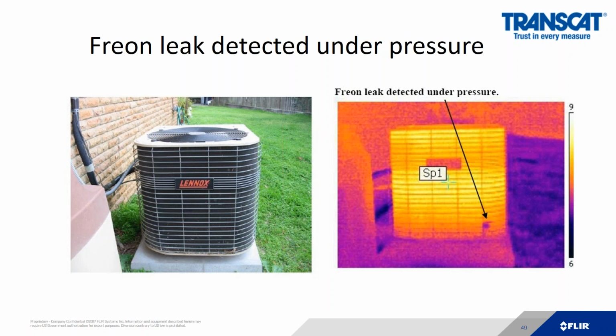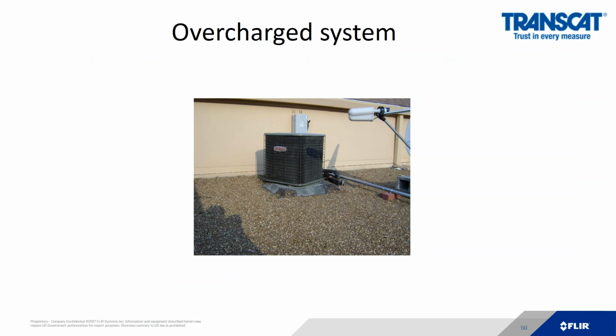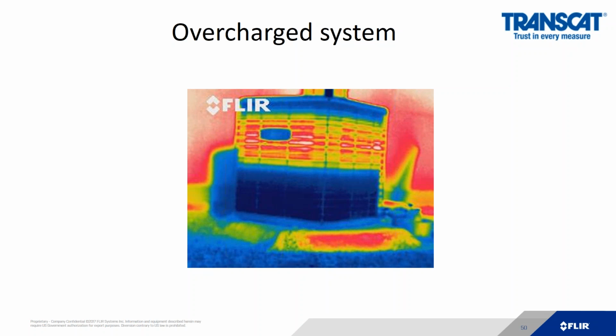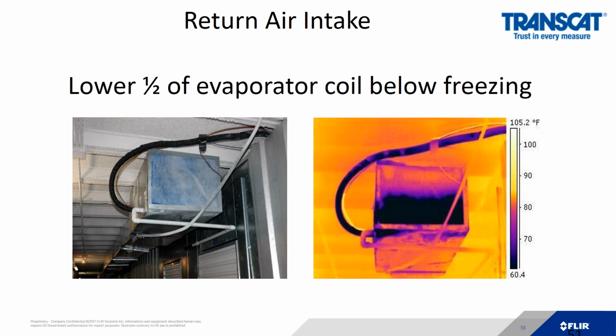Here, the customer, the thermal imaging camera user, detected a freon leak under pressure. We see this small little cold spot in the lower right-hand corner in the thermal image. Here's an example of an overcharged system. On a return air intake, the lower half of the evaporator coil is below freezing. With infrared, you are looking for anomalies. I would have expected to see a consistency across this target. The lower half is very, very cold.